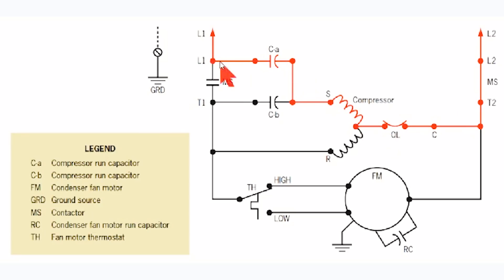When this switch closes, now you just have two capacitors in parallel that run the compressor. When the switch is closed, it makes no difference which side of the switch it's connected to. So now it's just additive - the two capacitances added together run the compressor. But what it does when it goes off is the interesting part.